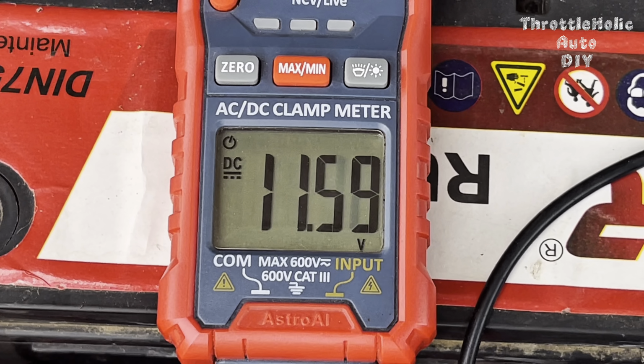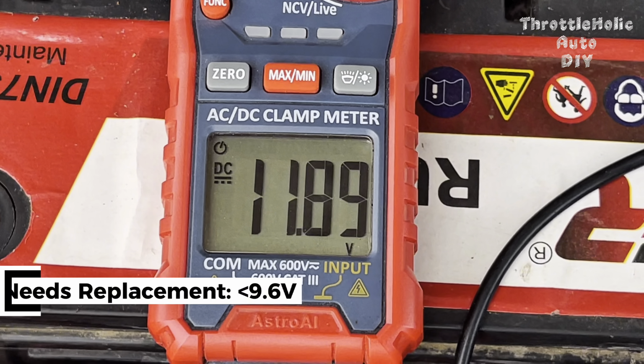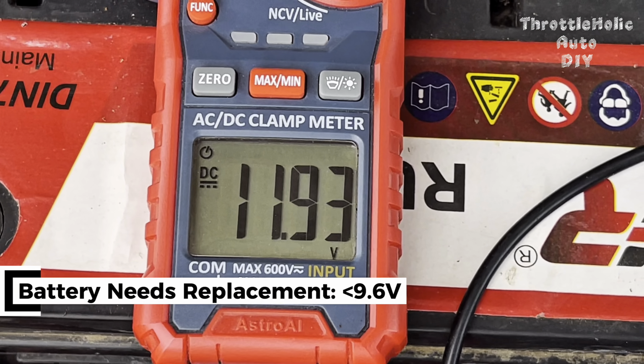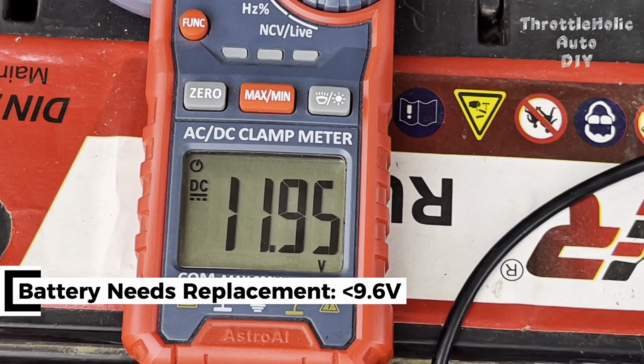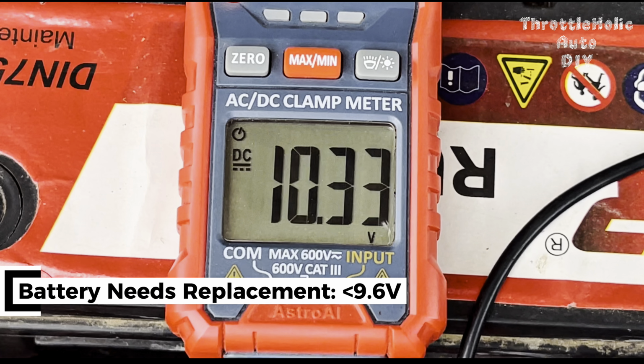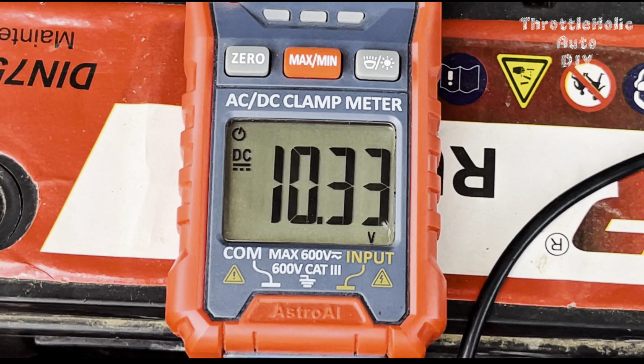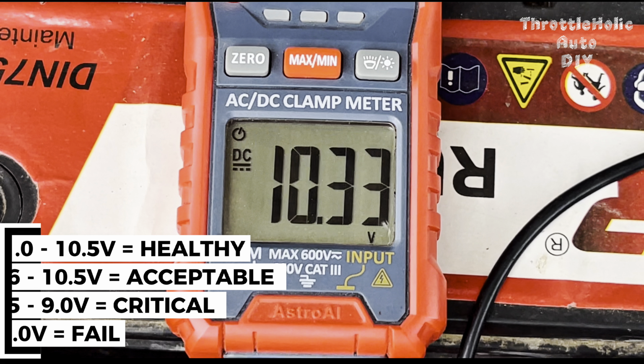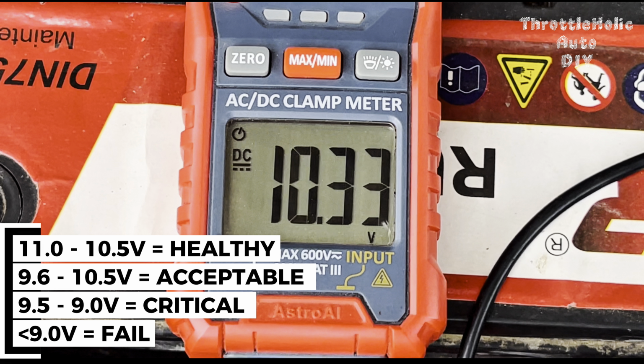If you have a drop less than 9.6 volts, you must begin to think of a replacement, or that battery will fail, especially as winter sets in. For reference, if you have a dip that falls between 11 volts and 10.5 volts, you have a healthy battery that will serve even through negative temperatures without issues.